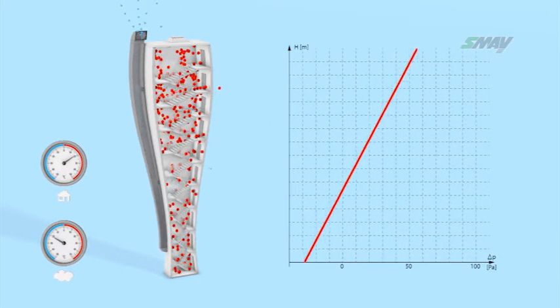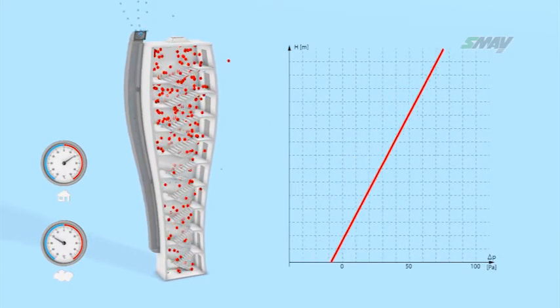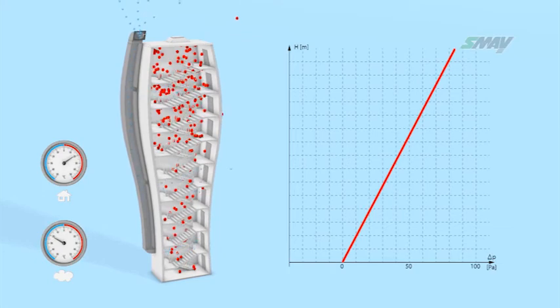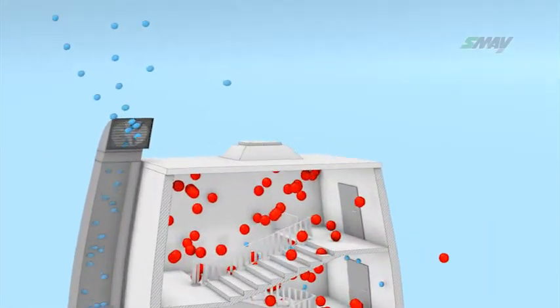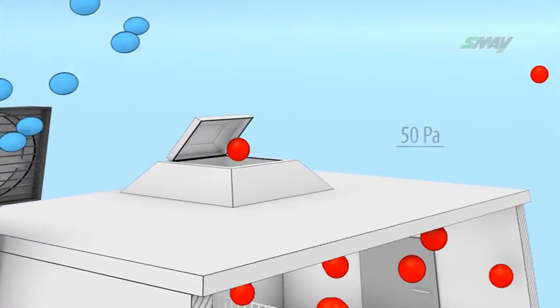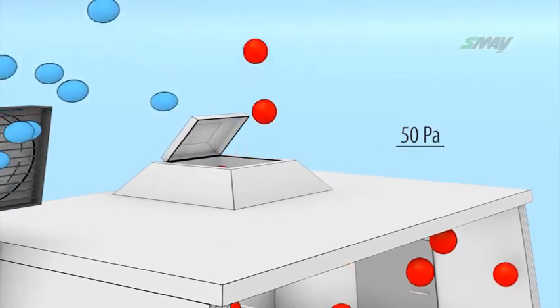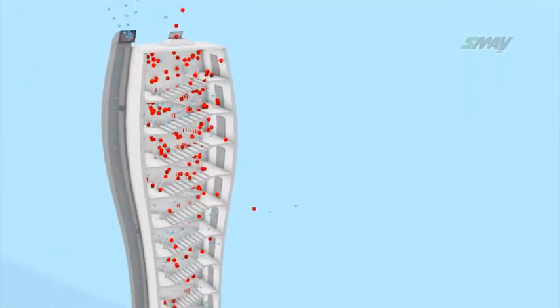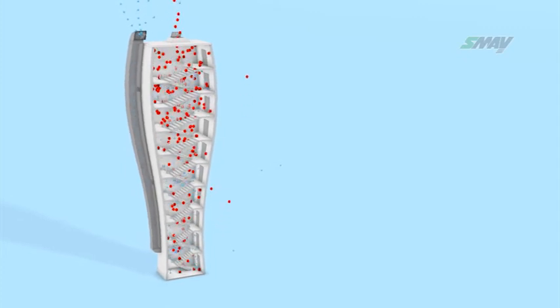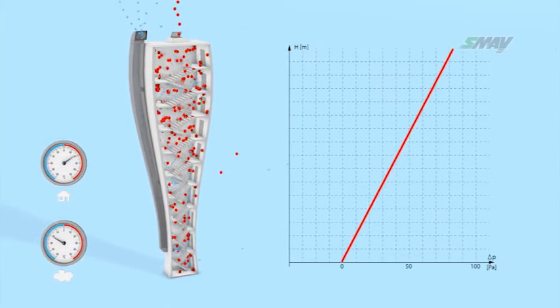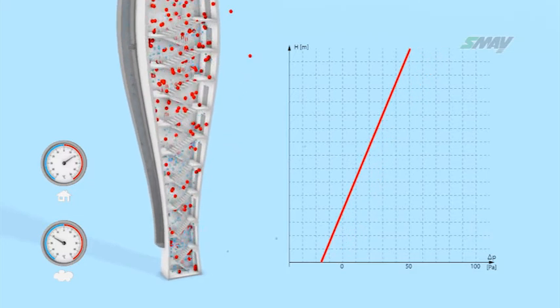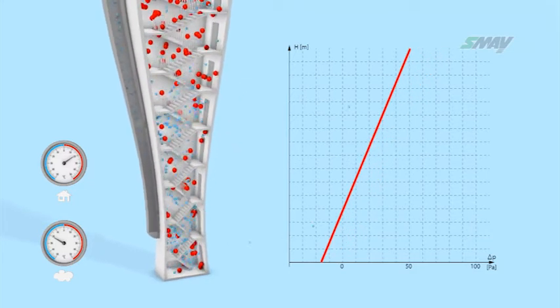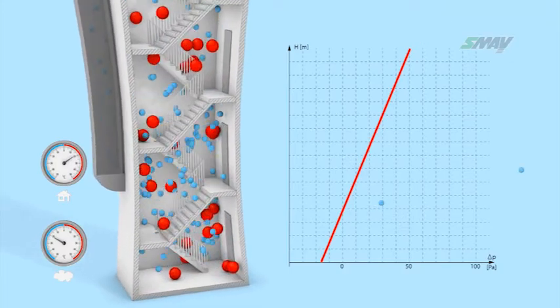Consequently, air pressure rises in the upper parts of the stairwell. The excessive pressure rise in the upper parts causes the barometric overpressure dampers to open, doing their job of maintaining pressure at no more than 50 pascal. The cutoff dampers only restrict pressure locally in the upper parts of the stairwell.